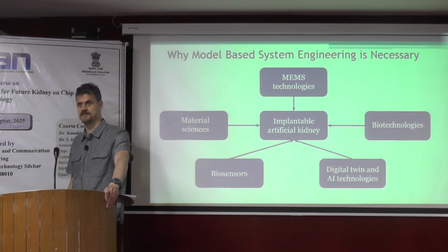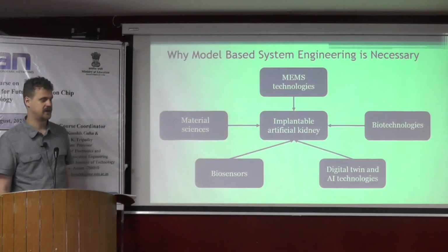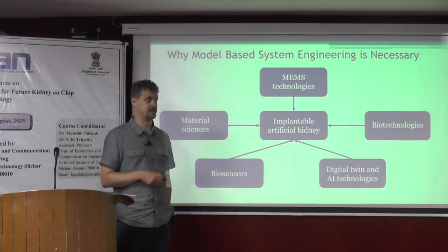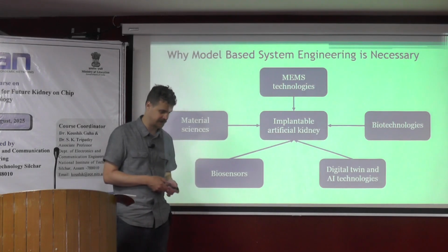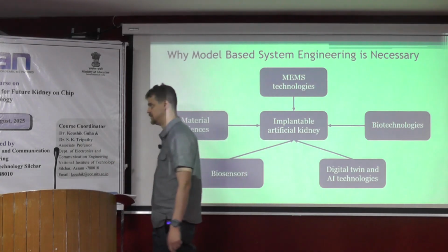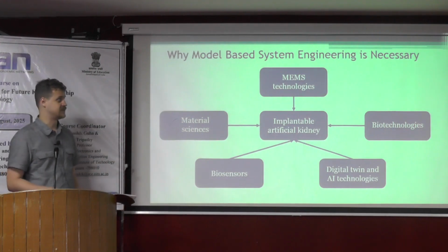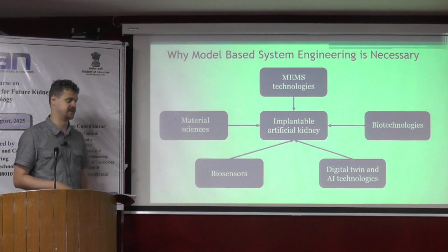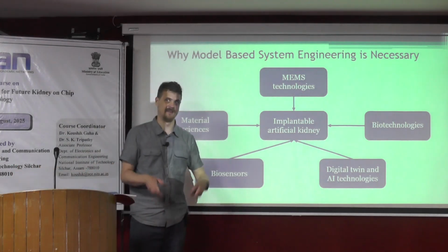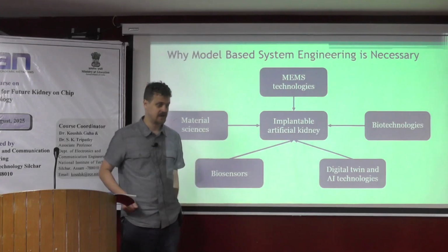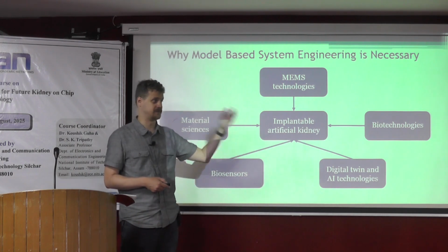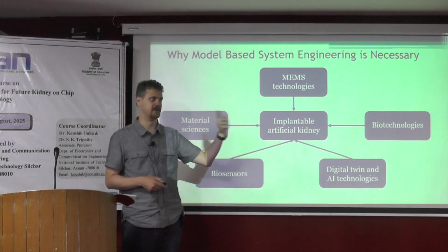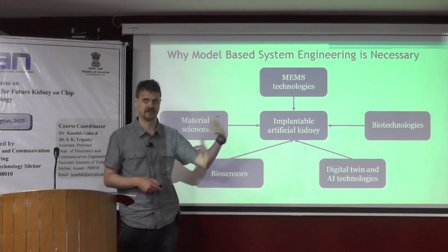And just like I said, there is a very huge issue with blood clotting in the case of the implantable artificial kidney. Wearable artificial kidney is developed specifically for hemodialysis, and we have the mass exchange unit that interacts directly with the blood. In the wearable artificial kidney we have a replaceable mass exchange unit that we use one time and then replace with a fresh one. In terms of the implantable artificial kidney, we have to develop a long-term blood filtration system that will constantly interact with the human blood.